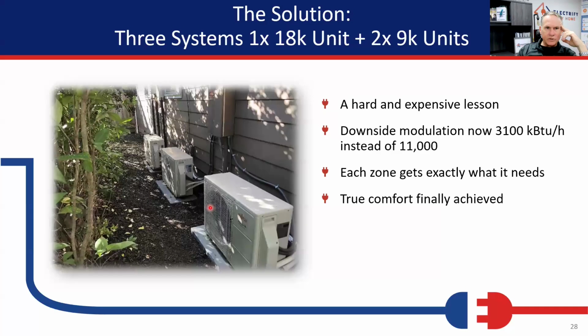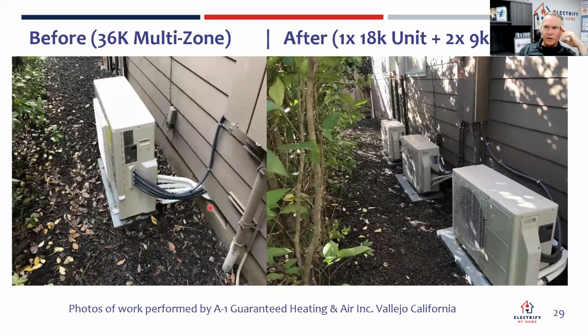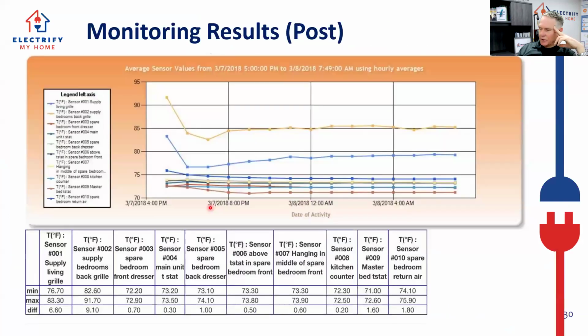But look at what the result was. That's the before and after shot of that one. This is what the result was. This is the temperature coming out of the register, the supply temperature, for the loose bedroom side. This is for the tight part of the house. So since those units can now operate independently of each other, those bedrooms can stay warm with 85-degree air coming out of their own system, and the rest of the house is able to maintain the temperature at this steady level of thermal equilibrium with air that's just 7 degrees warmer.